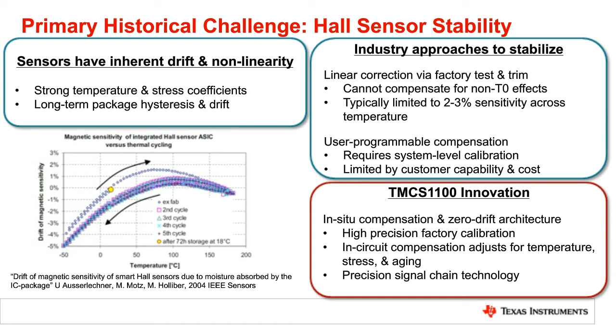When we look at the accuracy of a sensor, we talk about several different accuracy specifications. Before I get there, generally a sensor is considered a linear transfer function. You have current in, you get voltage out, and we have a couple specs that relate to that. Sensitivity is simply the gain or the slope of that transfer function, and offset is, of course, the offset in the y direction. What is your output when you have 0 amps as opposed to the ideal output?